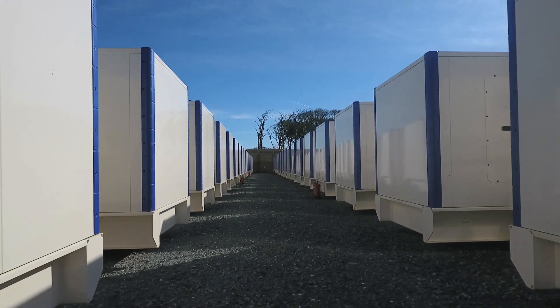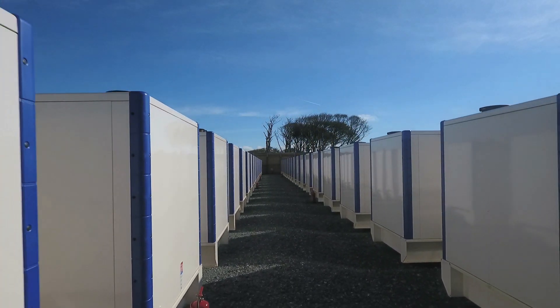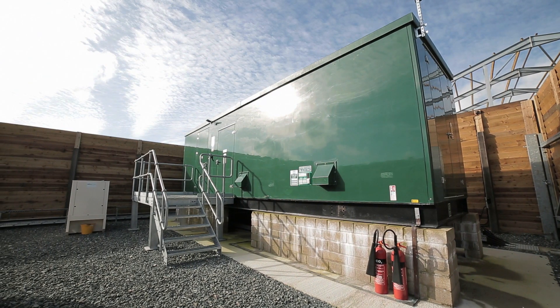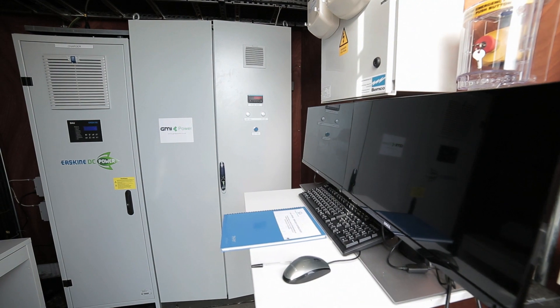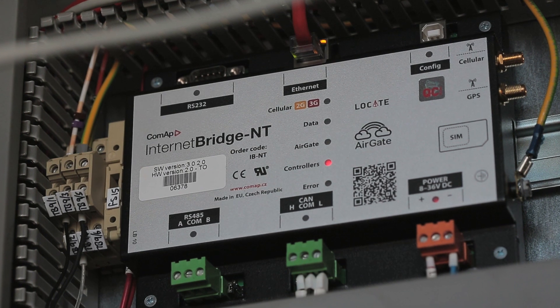Another thing that the generators can do is FFR — frequency response — whereby there's a relay from ComAp inside the generator control such that if the frequency drops just marginally below the standard 50 cycles, rather than wait for a signal from the outside world, the generators will start automatically.